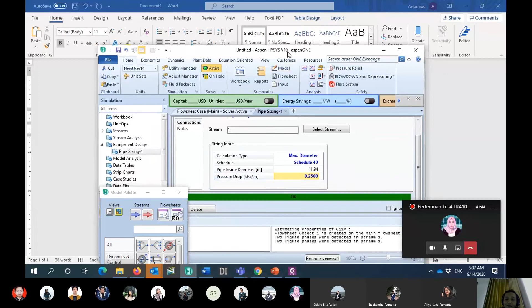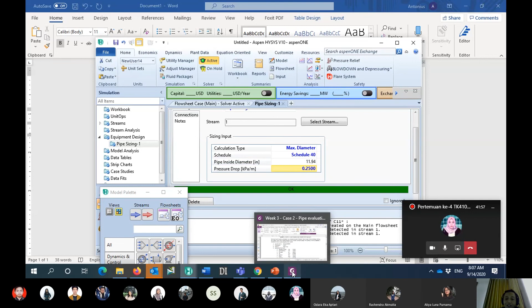Yeah, because my definition is in bar per meter, so I have to change the unit. It will be the same as 0.25 kilopascal per meter. And then the answer says the pipe inside diameter should be 11.94 inch. Check our existing pipeline. They mentioned that all the pipeline is 12 inch. So it is correct.